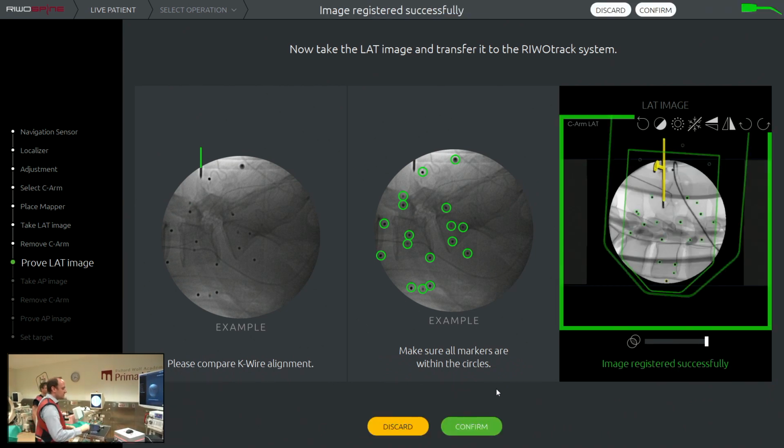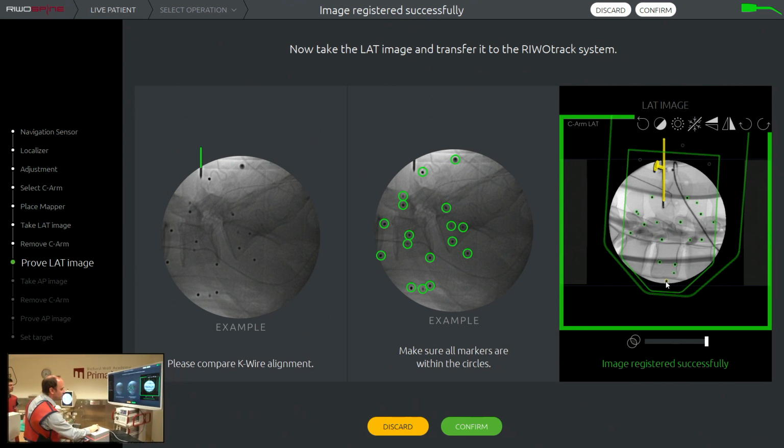And there we see in green here in the software, all these green spots are the fiducial markers that are recognized. Then here there's a yellow spot. That means there is a little bit of distortion in the image, but it's not a problem. We have enough green spots. Everything is green here. In case the precision would not be good enough, this would show up in yellow or even in red.